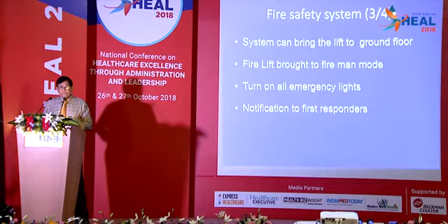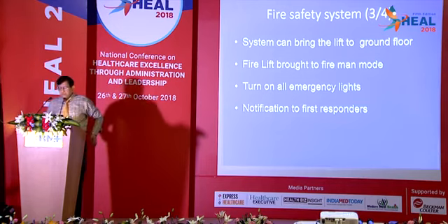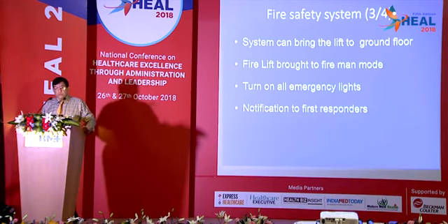The system can bring the lift to the ground floor. We can integrate the lift with the building management system, and in the event of fire, the lift can be brought down to the ground floor. The fire lift can be brought to fireman mode. We can turn on all emergency lights and notify first responders, and all this with the building management system.